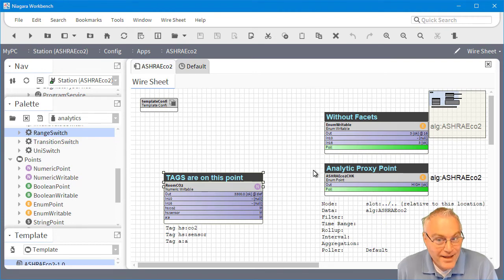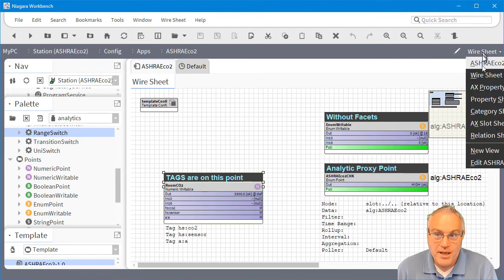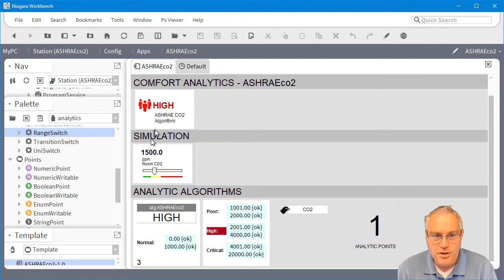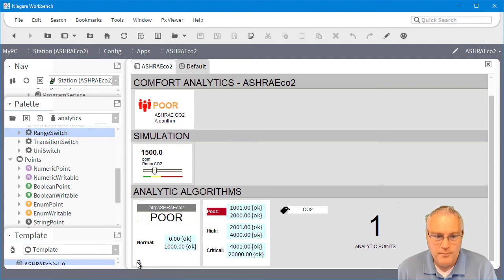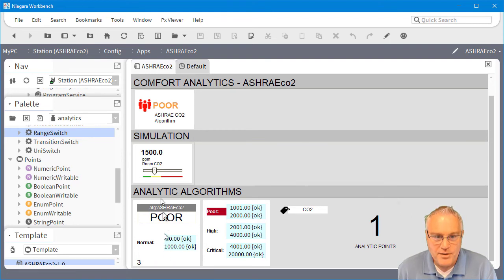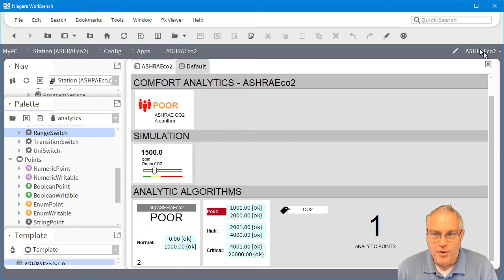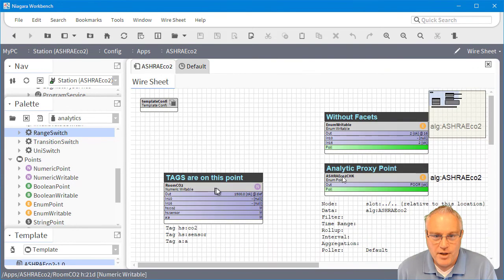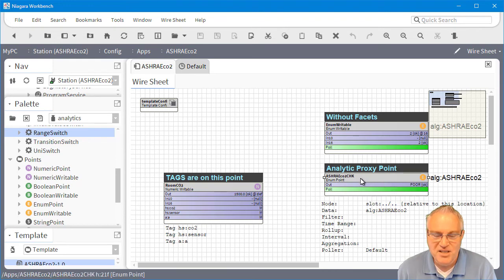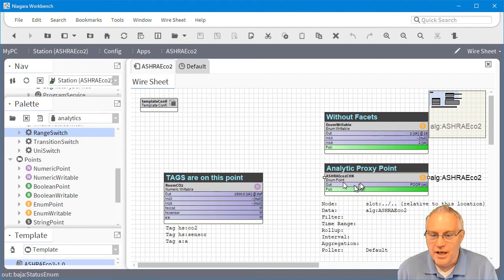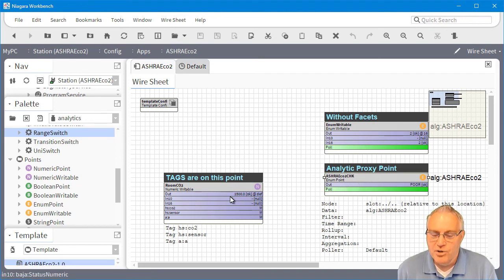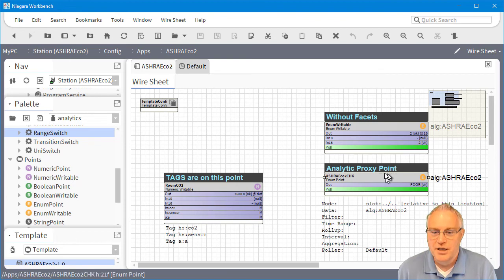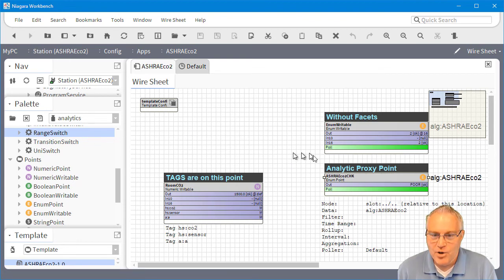With that, I'm ready to go with the PX page. This is the UI. This is just allowing me to change the values. I can go up here. Since I don't want to wait for the poller to go every five minutes, I'm just going to kickstart them there for this recording. You can see that they change. On the wire sheet here, right next to it is evaluating that 1500 and it says it's poor. So I can copy this and paste it anywhere in the station. It will execute and look right next to itself what that CO2 level is and report back whether it's high, normal, or poor. I don't have to memorize those ranges.